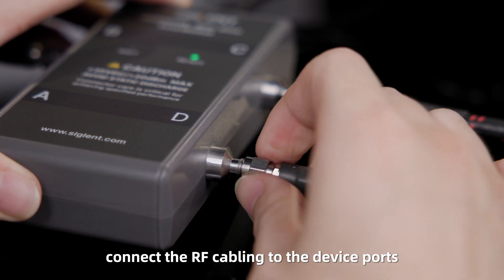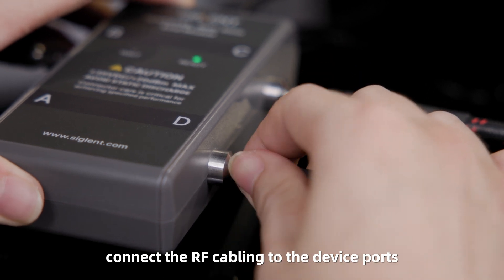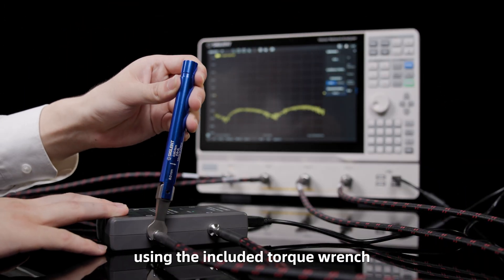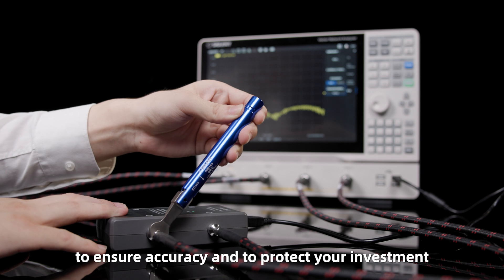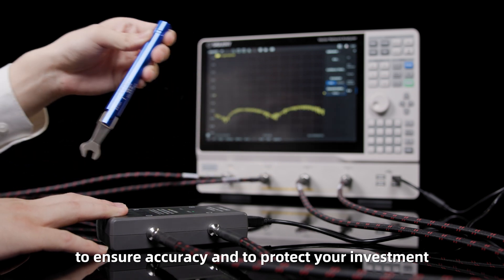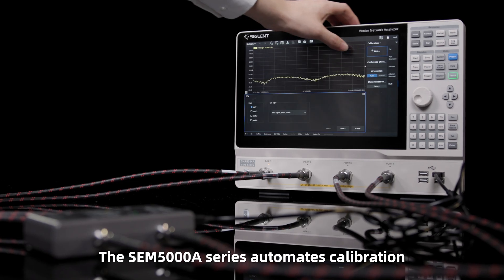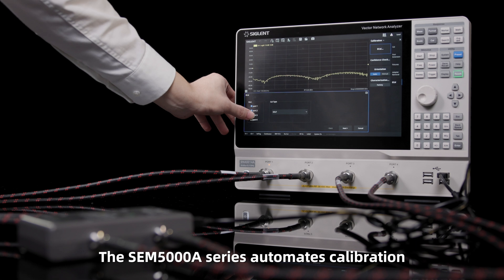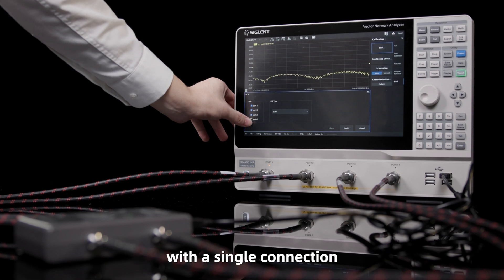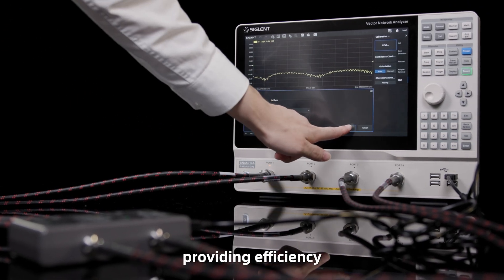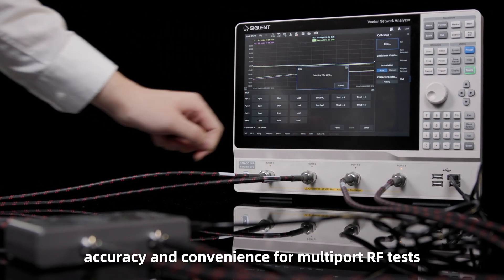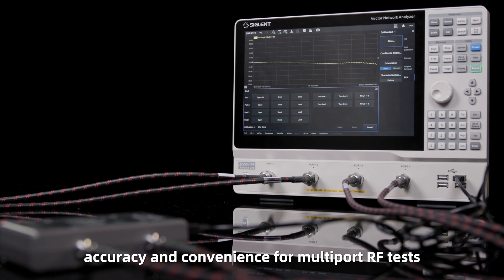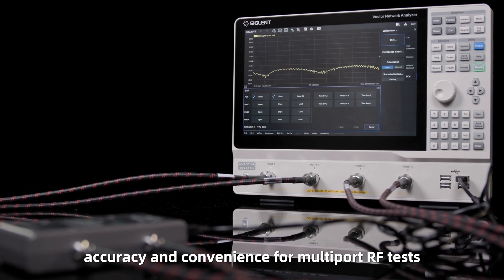Connect the RF cabling to the device ports using the included torque wrench to ensure accuracy and to protect your investment. The SNA5000A series automates calibration with a single connection, providing efficiency, accuracy, and convenience for multi-port RF tests.